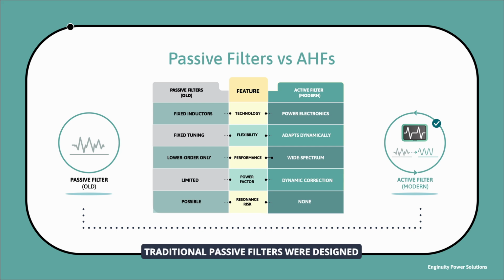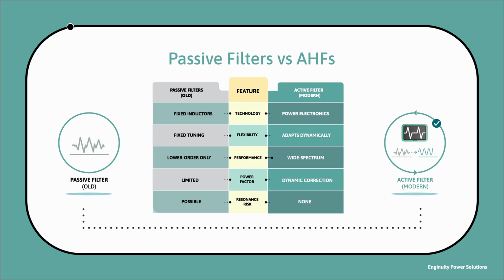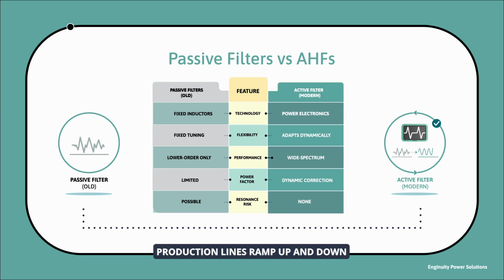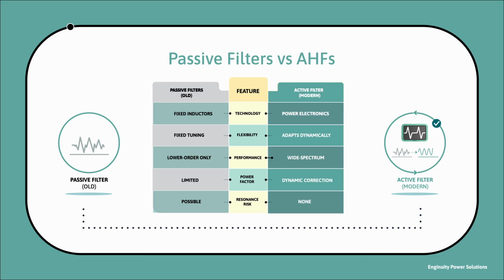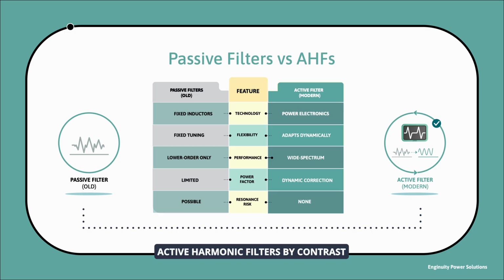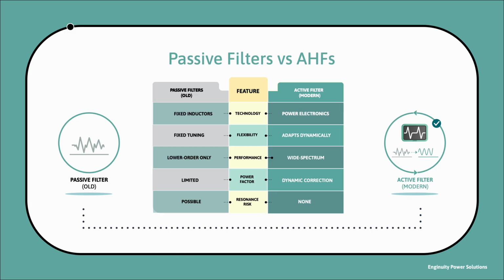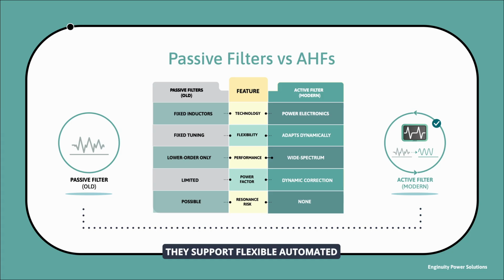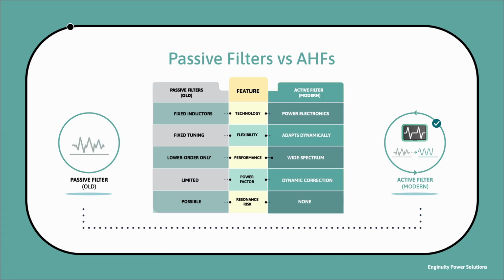Traditional passive filters were designed for fixed, predictable loads. However, modern facilities are dynamic. Production lines ramp up and down. Robotic systems vary their duty cycles. Electrification continues to expand. Passive solutions cannot adapt to these changes. Active harmonic filters, by contrast, respond dynamically in real time. They support flexible, automated environments without constant retuning or redesign.